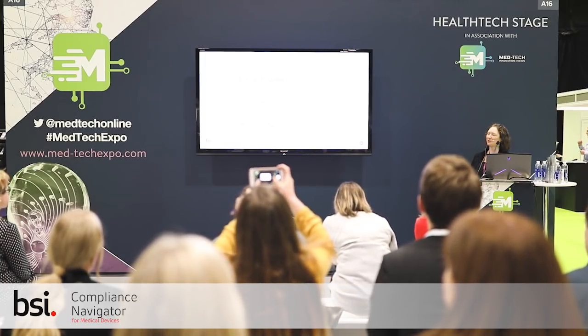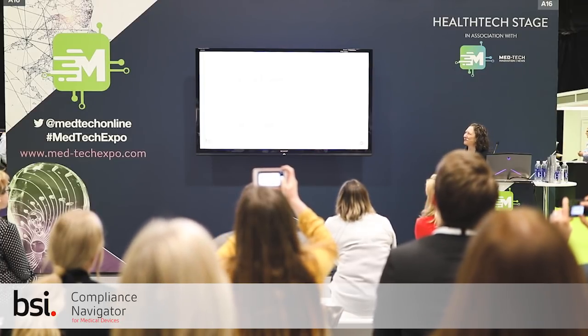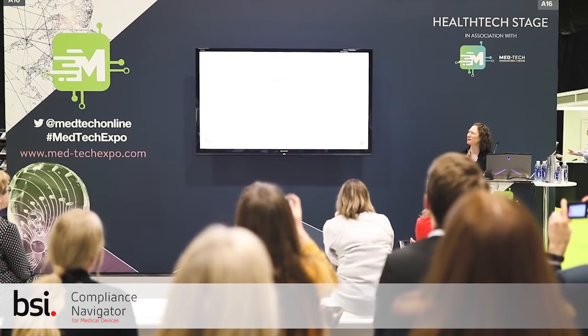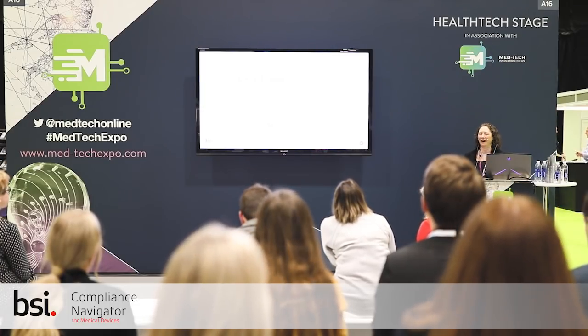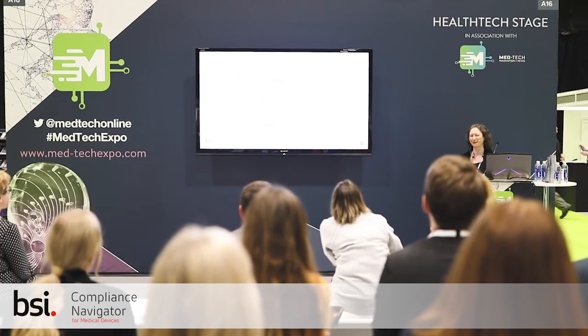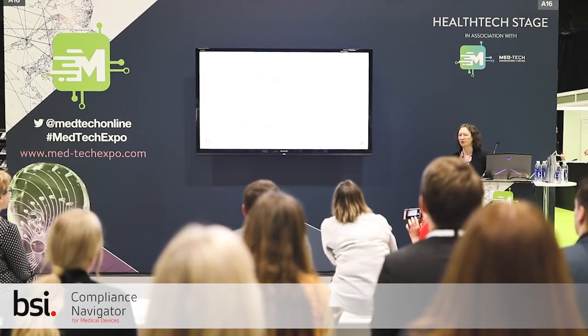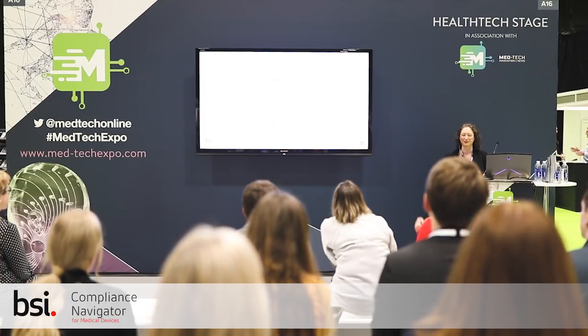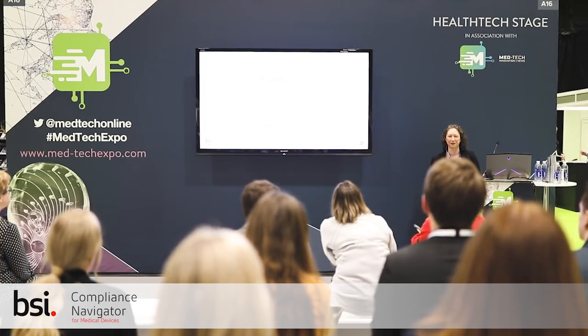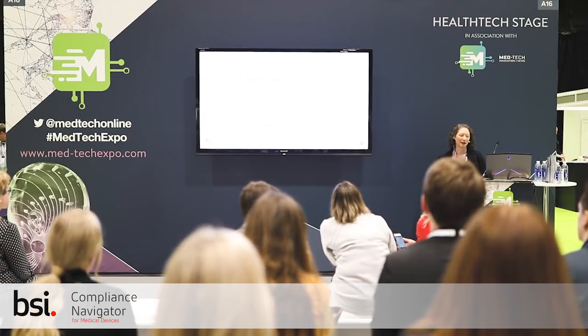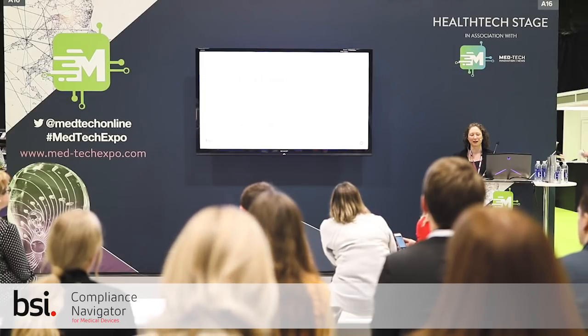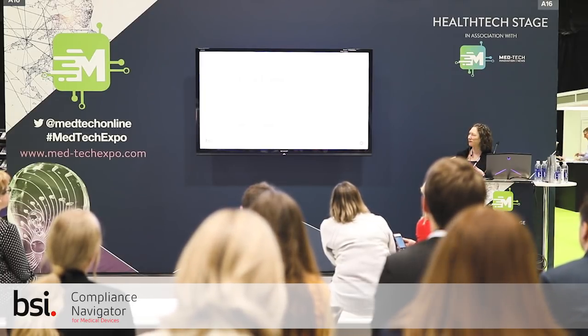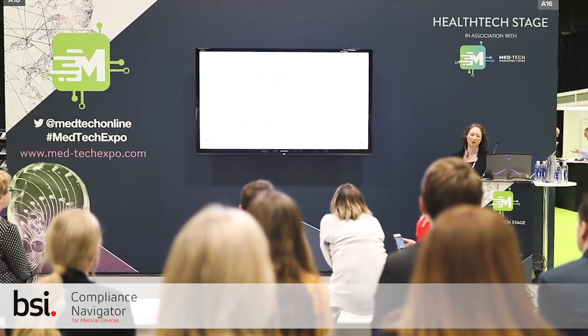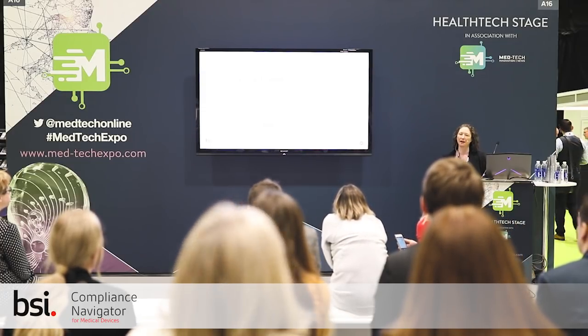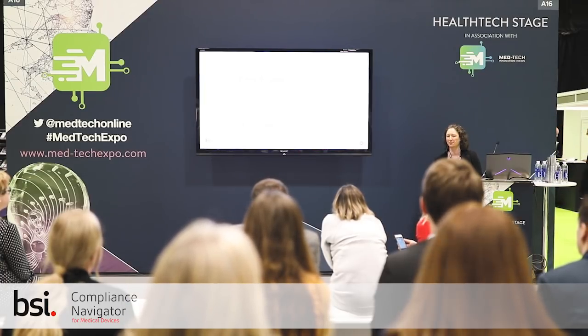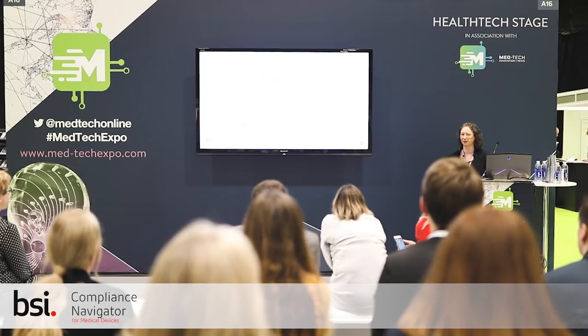And finally, that there should be sufficient data and quality, a sufficient amount and quality to allow a qualified assessment. What does sufficient mean? It's a really qualitative word, and I think it's really hard to know what that is. I think there's going to be a lot of discussion about what sufficient is between manufacturers and notified bodies and competent authorities. I think sufficient information should be able to answer the question as to whether something is safe and is performing. And if you can't demonstrate that it's safe and you can't demonstrate that it's performing, it's probably not sufficient clinical data.